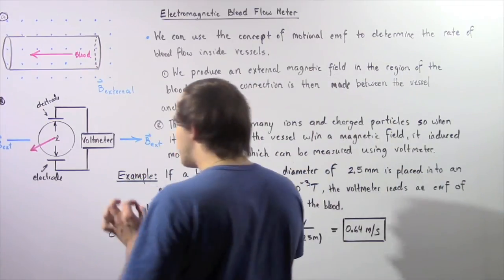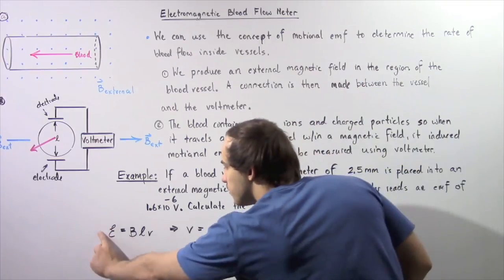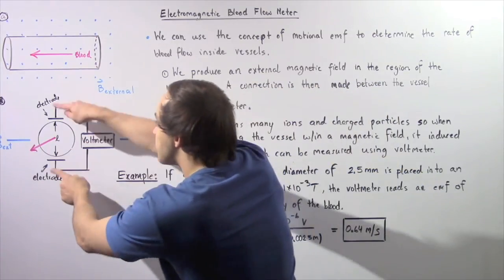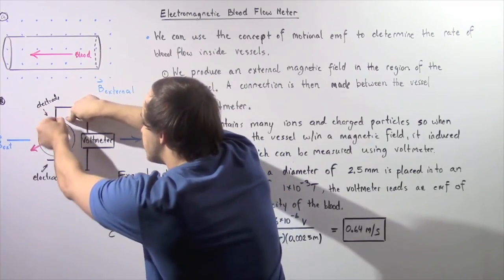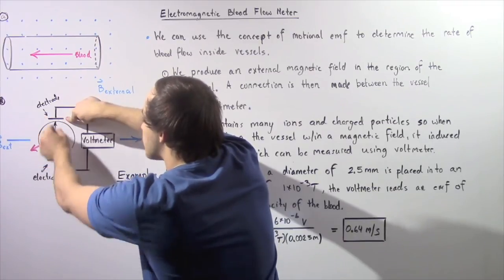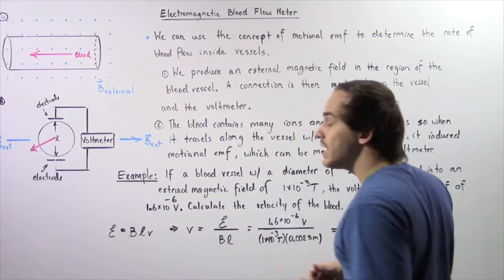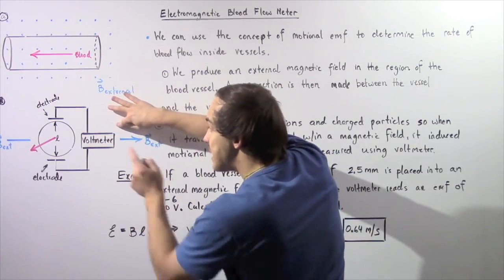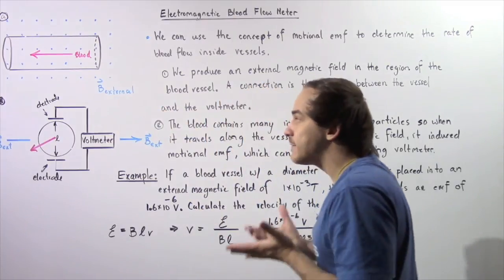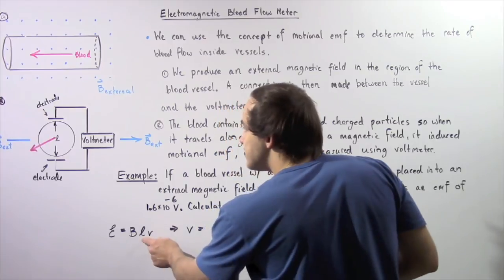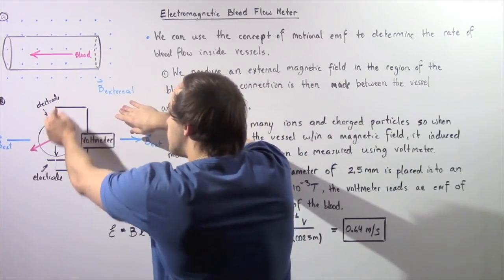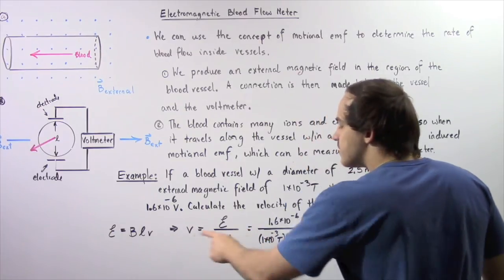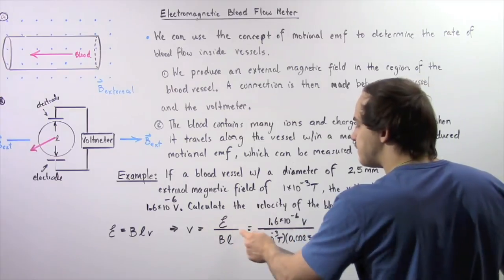We use the equation derived in the previous lecture: the Motional induced EMF equals the product of the external magnetic field B, the length L (the distance between the two electrodes, which is the diameter of the blood vessel), and the velocity of the blood. The EMF is measured using our voltmeter, B is the magnetic field we create, and L is the diameter of the blood vessel. Rearranging, the velocity equals the induced EMF divided by B times L.